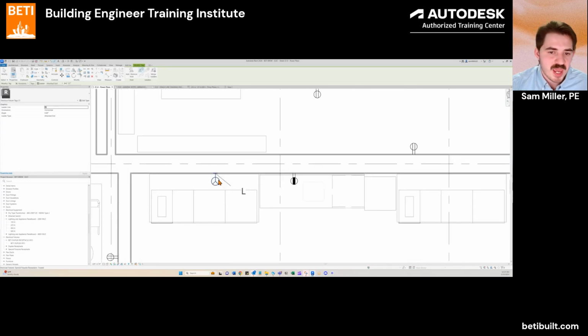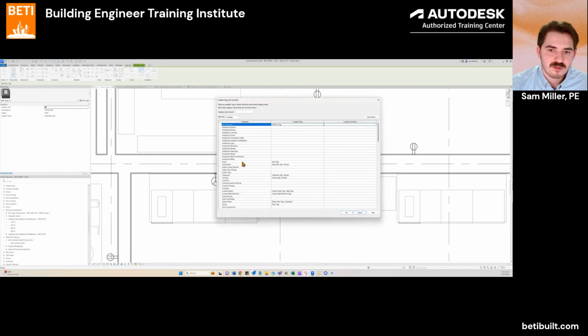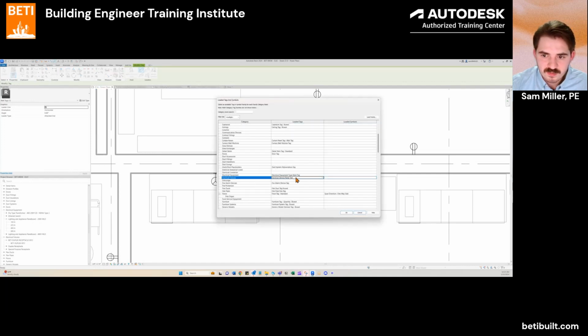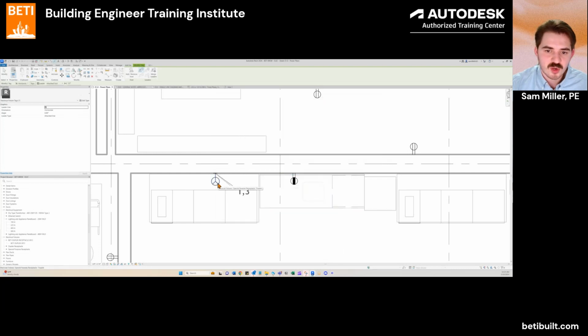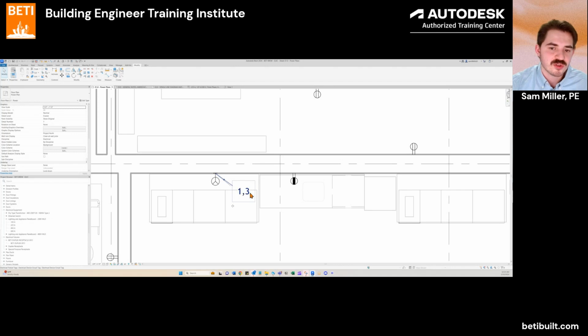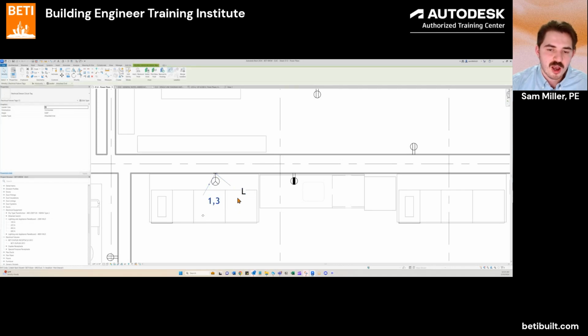This is giving me the panel that is associated with it, and if I add another tag and select the circuit tag, that will say 1-3, the circuit that Revit now knows is linked, so I can tag it. But this doesn't look great, right? We want these to be combined into one tag.